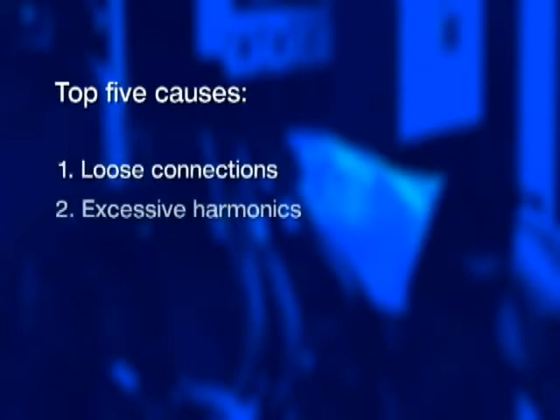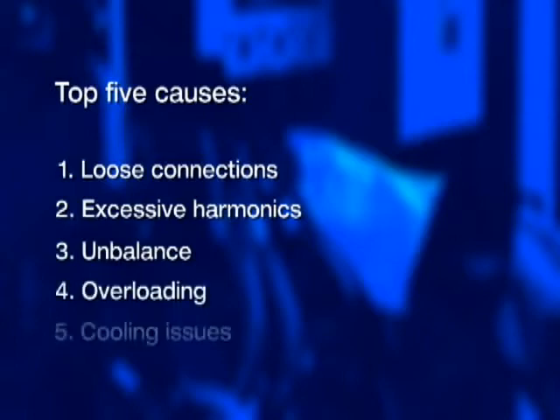Unfortunately, some of these problems occur intermittently. So what you're going to have to do is log some data over time and then go back and analyze in order to find your transformer problem. The top 5 things that commonly cause transformers to vibrate or buzz or hum excessively loud are loose connections, excessive harmonics, unbalance, overloading, and cooling issues.